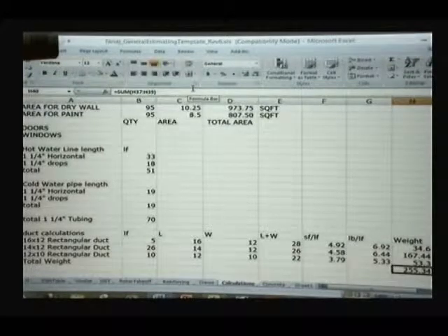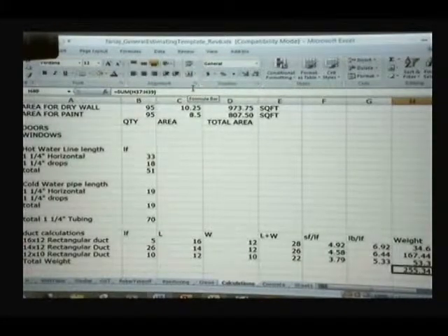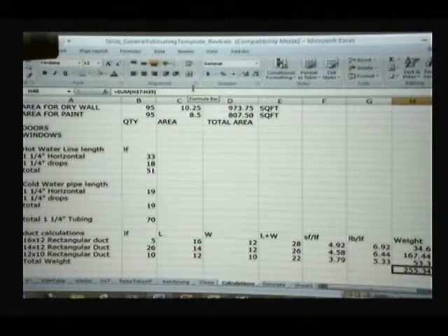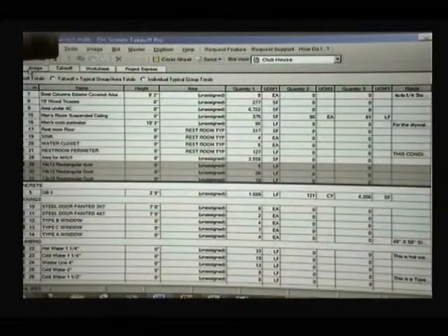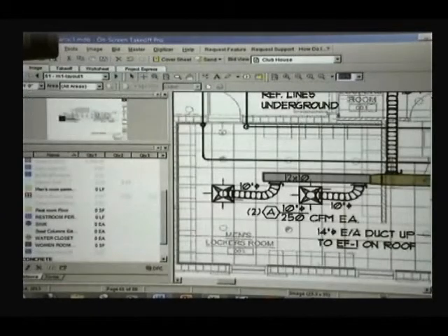Well, see, the problem is that you're going from a larger section to a smaller, right? So if you take the smaller one and pull it back, you're going to be short on material. If you take the larger one and pull it forward, you're going to have more material than what you need. So it's normally safer to go on the larger side. It's a small section anyway, so it doesn't really matter too much, but if you keep doing that consistently, all of a sudden you're going to be underestimating the materials.